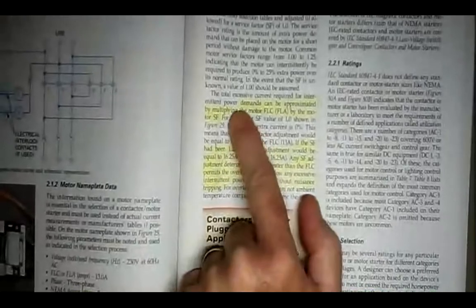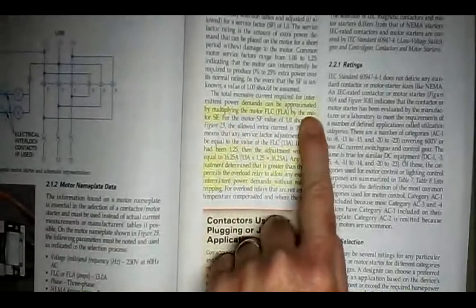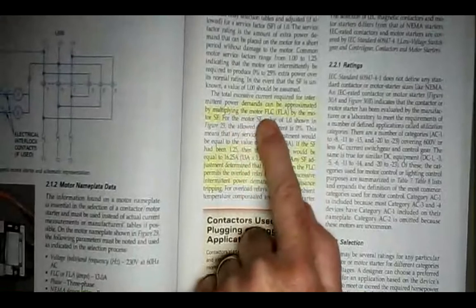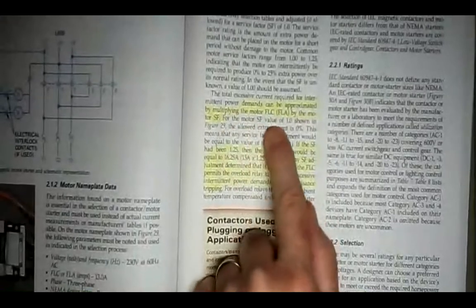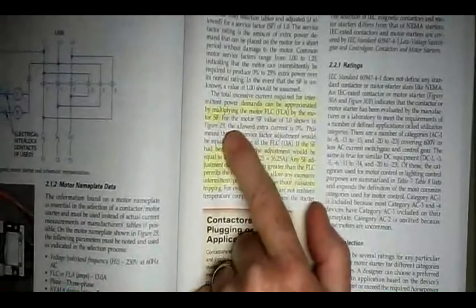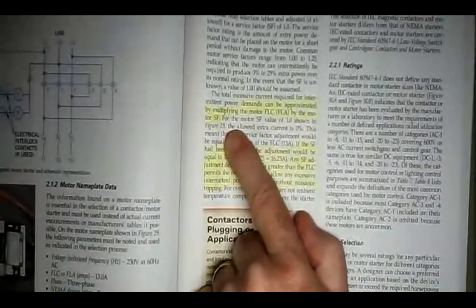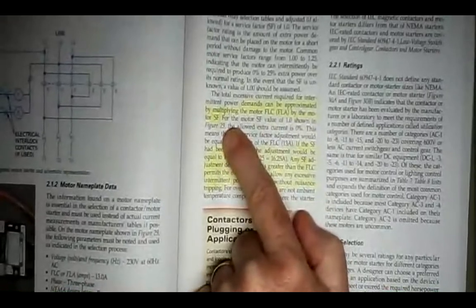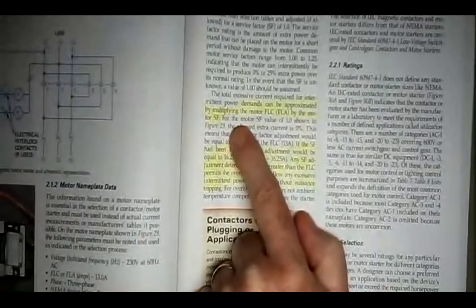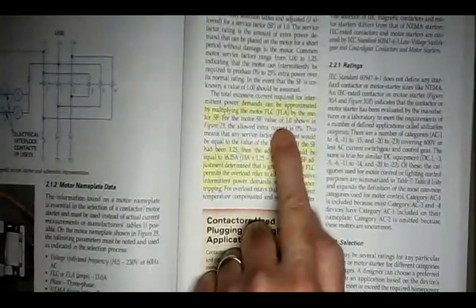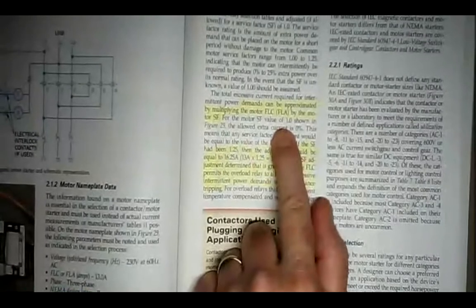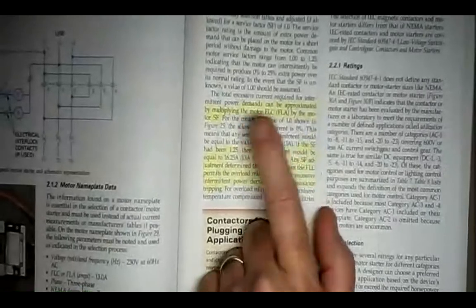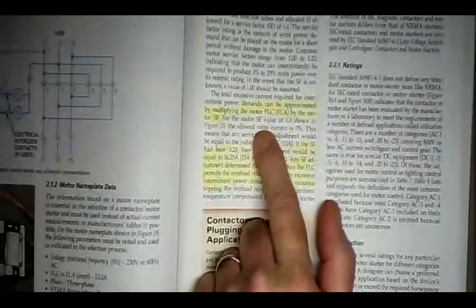left-hand side says the total excessive current required for intermittent power demands can be approximated by multiplying the motor full load current by the motor service factor. And that's what we were talking about before. The service factor might be 1.15. You can actually overclock that motor. You can get 1.15 out of that motor. So if it's a 10 horsepower motor, you can get 11.5 horsepower without causing any detrimental damage to the motor.